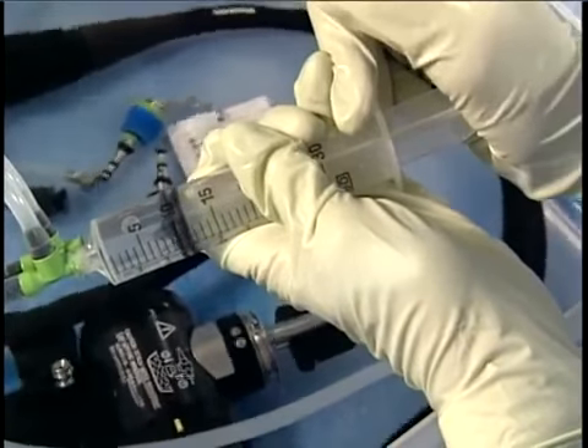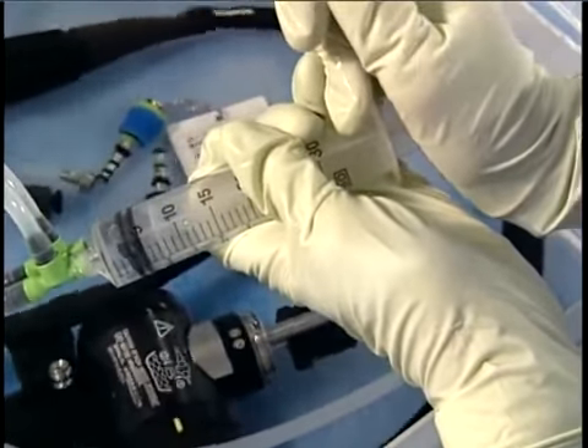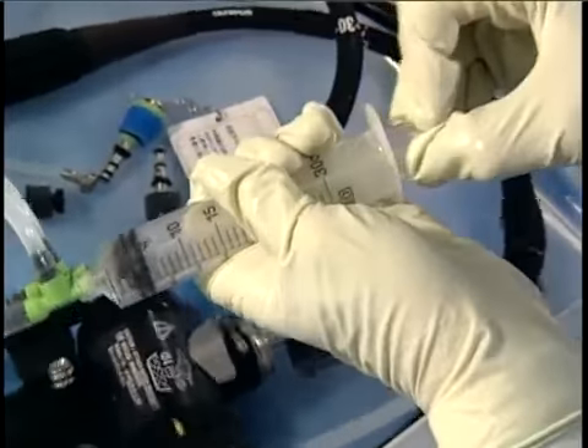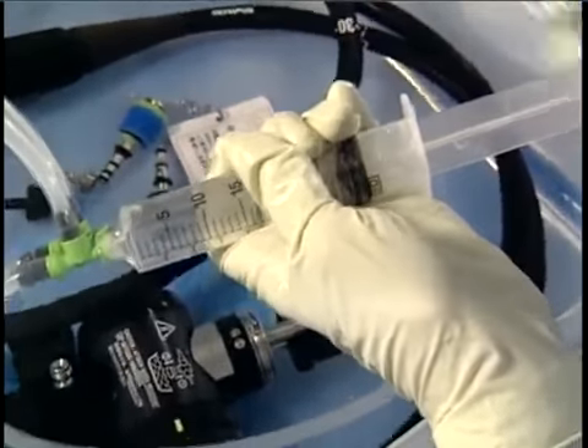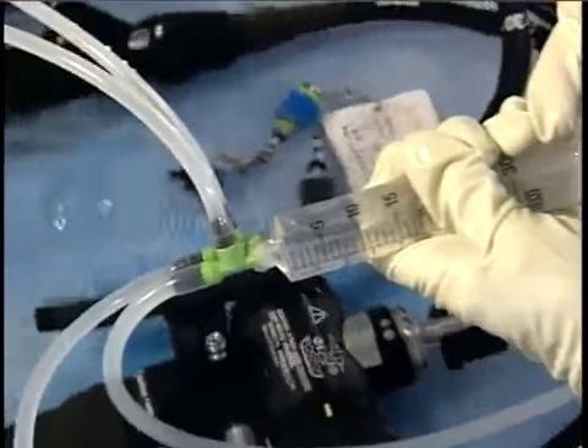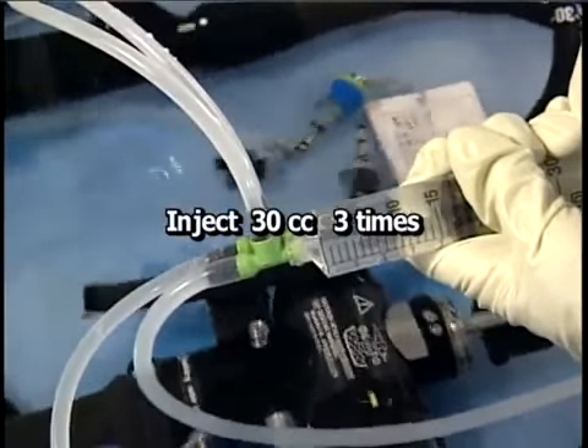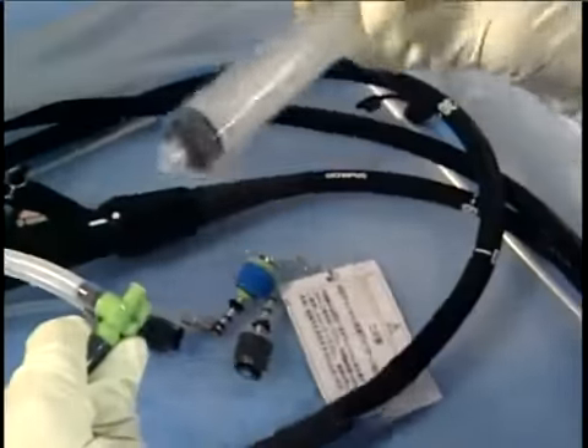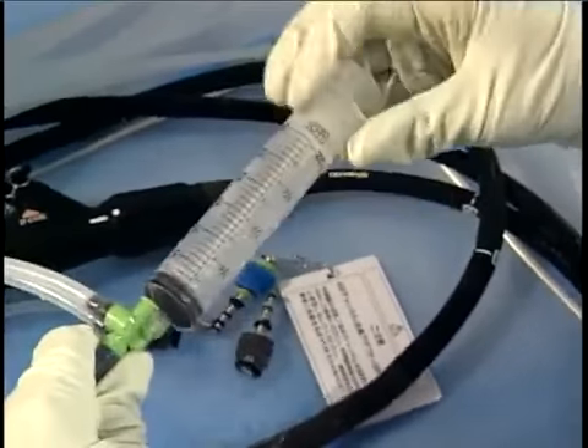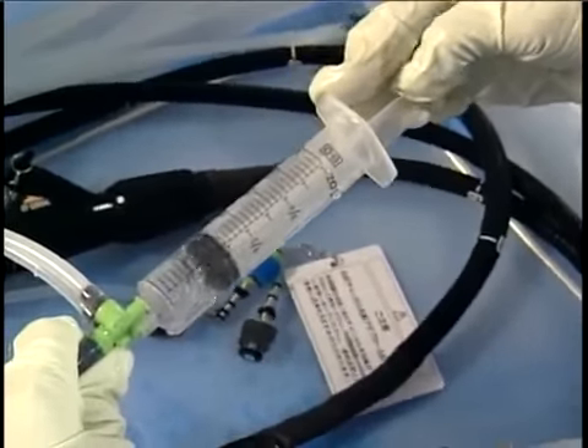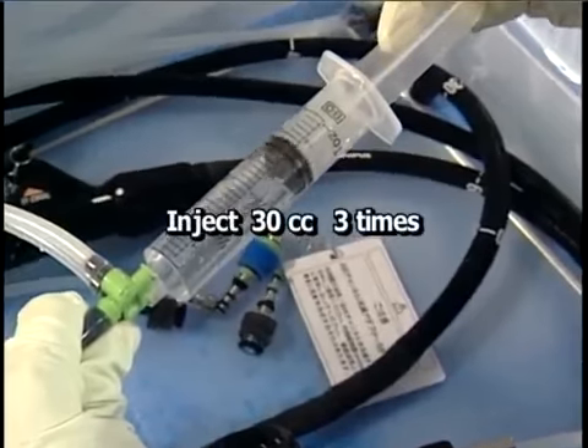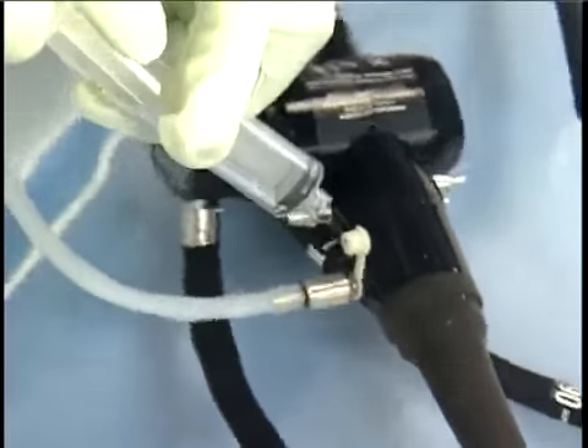Now, rinse the channels. With the suction intake filter in the water, use the syringe to flush 90 cc's of water through the suction channels. Move the syringe to the air-water port and repeat to flush rinse water through the air-water channels. If you are reprocessing an endoscope with a special channel, use a syringe to inject water into the auxiliary water channel.